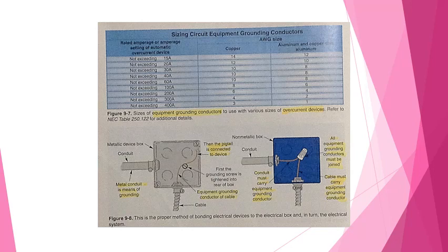Referring to Article 100 of the National Electrical Code, bonding is required at all conduit connections at the electrical service equipment. Points where a non-conducting substance is used that might impair continuity, that is, where current may not be able to flow past the non-conductor. Such bonding is done by connecting a jumper around the non-conducting substance.